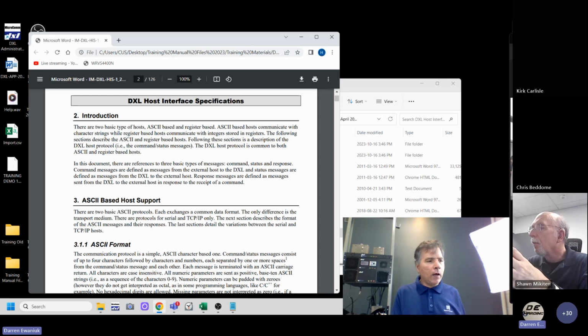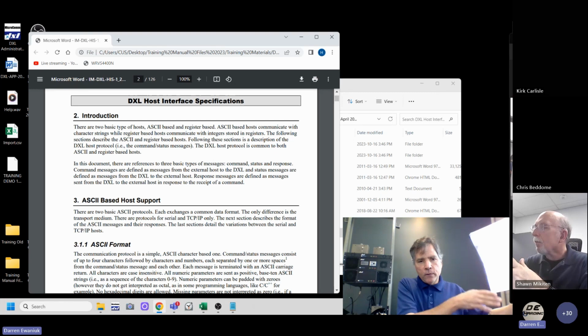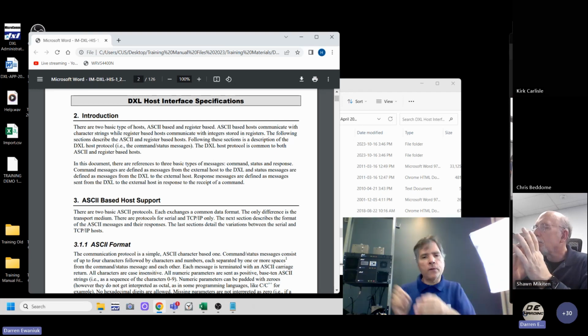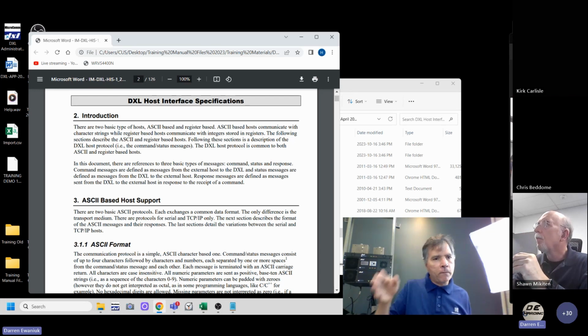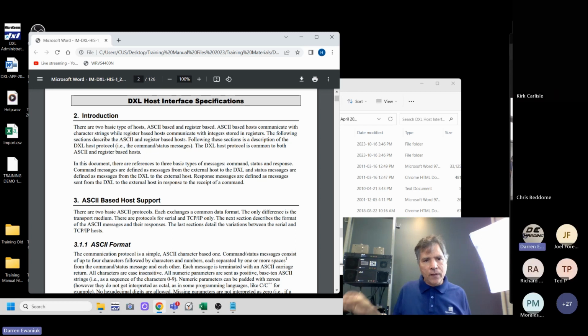What we do on our PLC type systems is take the text equivalent. You have a command and then 4 additional arguments, so we have a sequence of 5 sequential registers in our PLC. Those are the command registers that you would send commands to. You would send the command in the first register, the first argument in the second register, the second argument in the third register, etc. So instead of sending a text string, you fill out 5 register blocks, which does the same thing. It's the same format as a command and then the arguments.